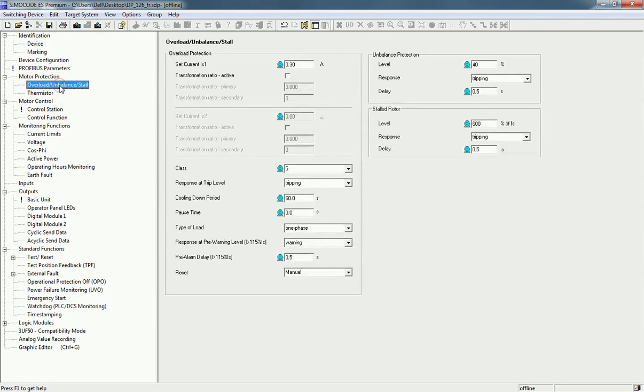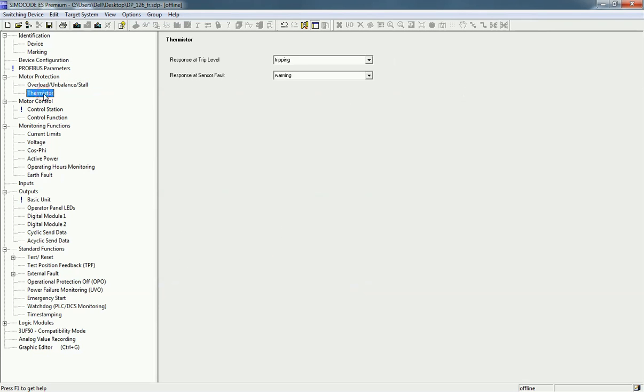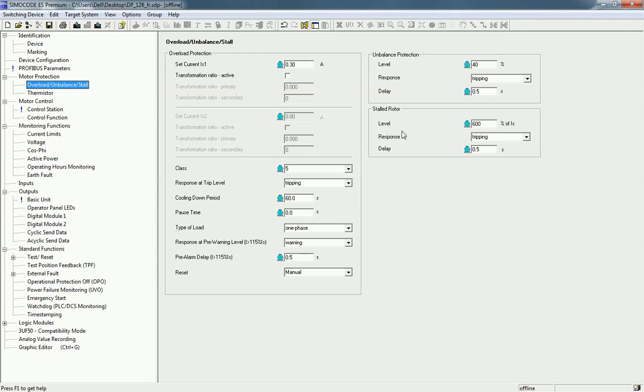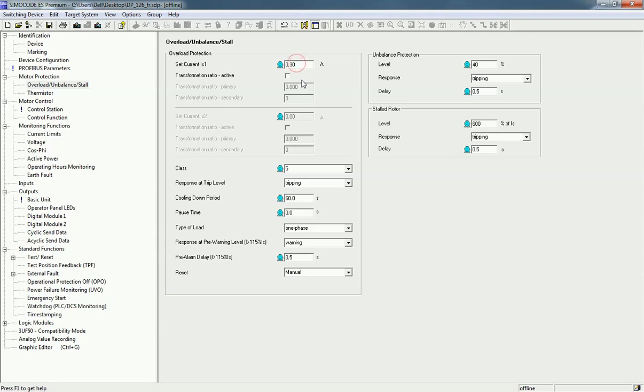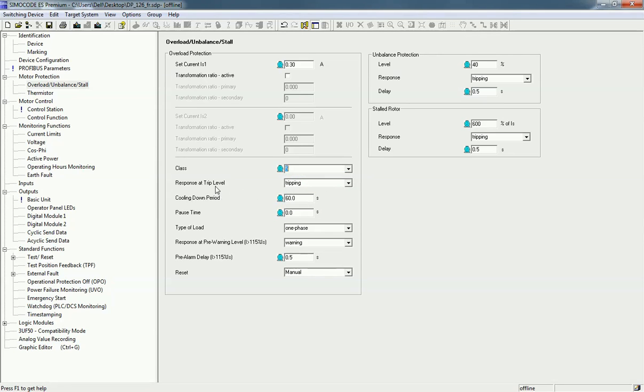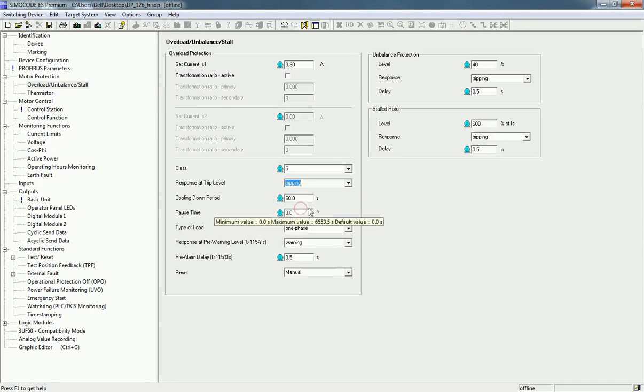In Motor Protection, we have two options: Overload and Thermistor. For Overload, first we set the current — as per your load you can define the current capacity. When you click on the cursor, you get the minimum and maximum range by default. I will keep 0.30 ampere. Next we set the motor class — there are different classes available. For the response at trip level there are four options: disable, signaling, warning, and tripping. I will select tripping.